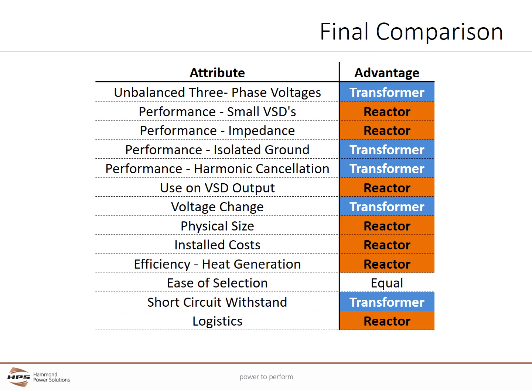Final comparison. In summary, reactors and transformers offer the user many advantages. Reactors can be used with smaller VFDs, have better impedance selection and performance. They can be used in a VFD output without derating. They are smaller and have a lower installed cost, and are easier to transport and generate less heat while energized than drive isolation transformers. Drive isolation transformers can create isolated grounds and help better with a variety of power distribution issues, such as unbalanced voltages. They can do actual harmonic cancellation, they can change the voltage as needed, have no voltage drop, and act as current limiting devices during short circuit faults.